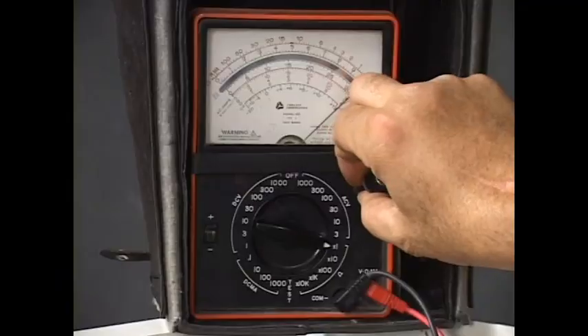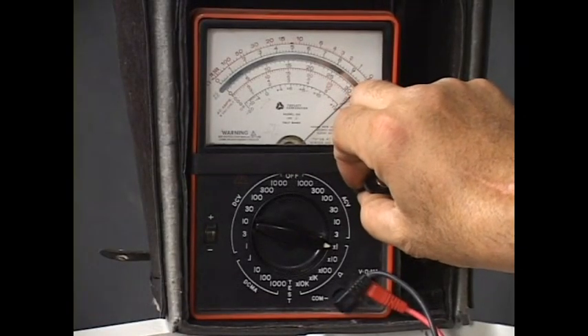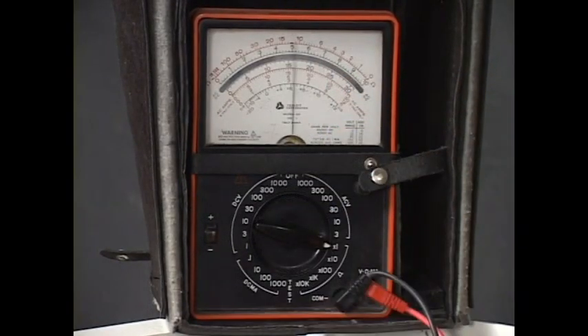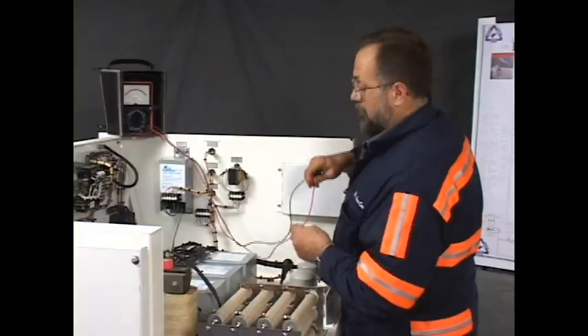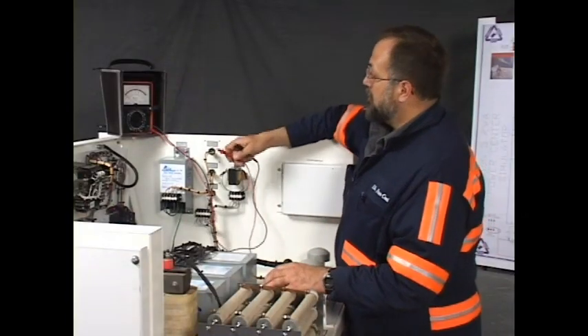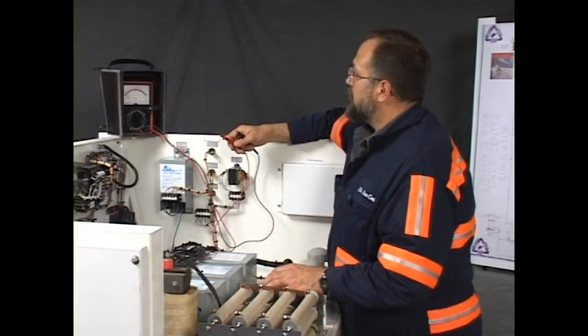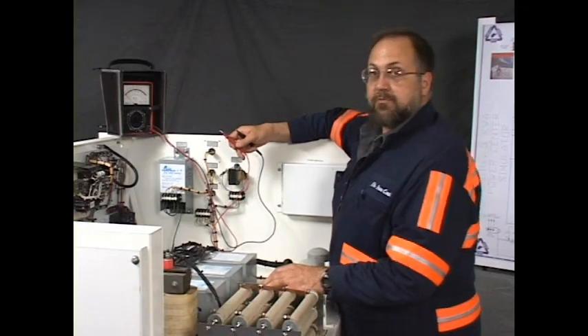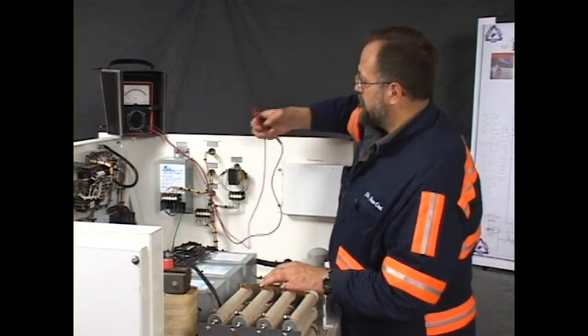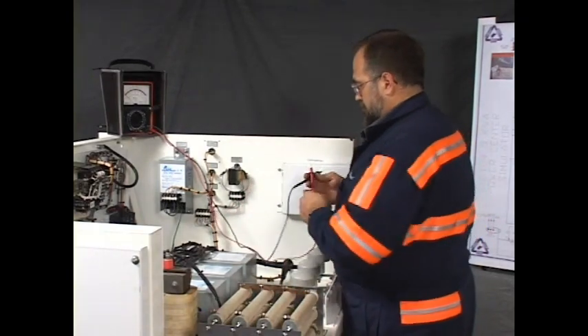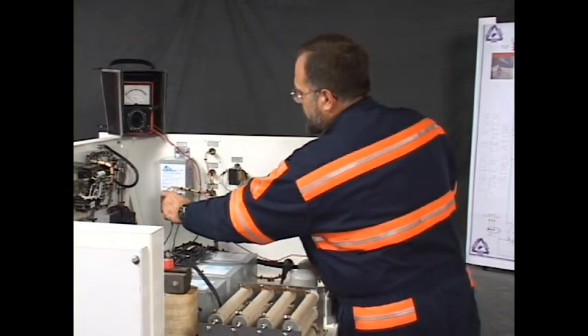Calibration of the instrument is important. Sometimes problems are not always on or off. Sometimes they're just in degrees of difference, just a few ohms difference. If your instrument's not zeroed, you won't detect that. It just takes a moment to do.